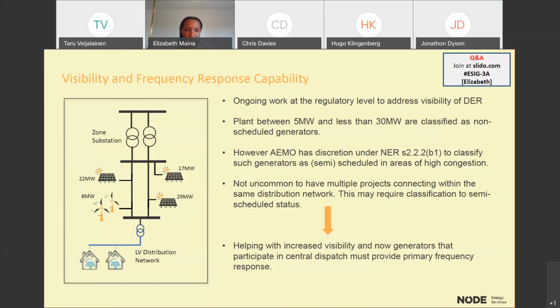So considerations from that perspective include ensuring these smaller projects, even though they're connecting at the distribution level, by virtue of being in an area of high congestion and getting categorized as semi-scheduled, will need to provide primary frequency response. We need to work with these projects to ensure they're tuned to provide frequency response within the dead band of 0.015.